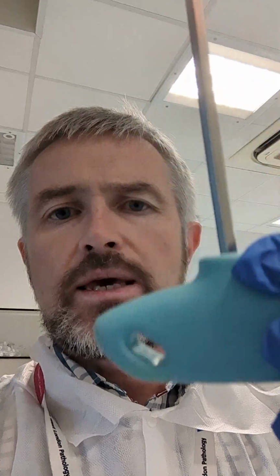Right, final point, again that is useful to know, is what happens if the lid won't open and my samples are stuck in the centrifuge. Okay, within a drawer somewhere nearby or being delivered with your centrifuge will be a centrifuge key. Now this will manually override the lid. The lid has a safety feature which won't allow it to open in operation. So before you manually open a centrifuge, you need to be absolutely certain that the centrifuge is not spinning, because it will override this. So the best way to do it is ensure that the cycle is finished.